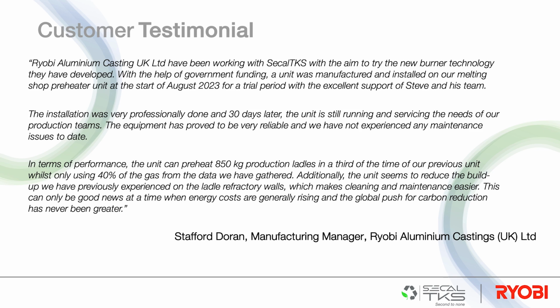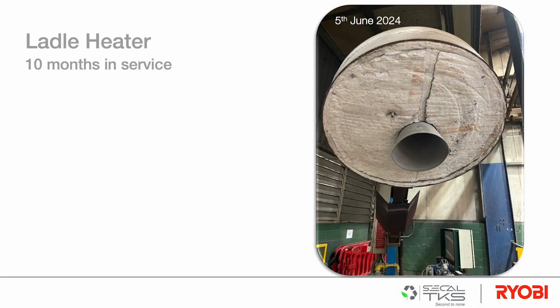I was there a week yesterday on the 5th of June. That is the unit today. There's no sooting up and carbonisation that you get from using a burner. There's no scale. We've had zero service calls as well, which is fantastic. Zero scale formation on the energy deflector cone. And we use the deflector cone because we've not got castable. It would render it too heavy.